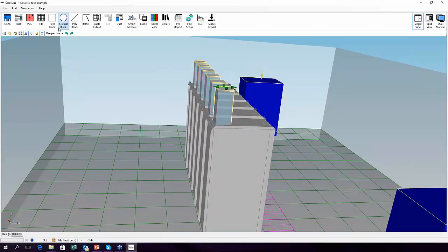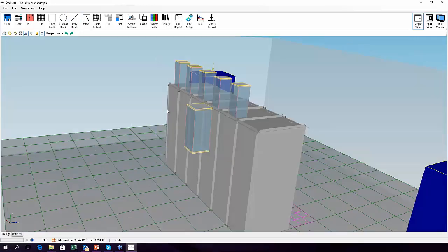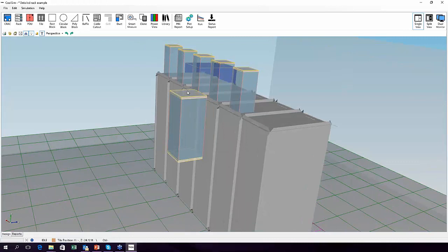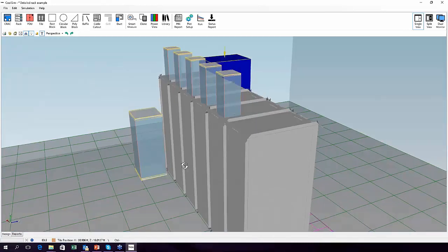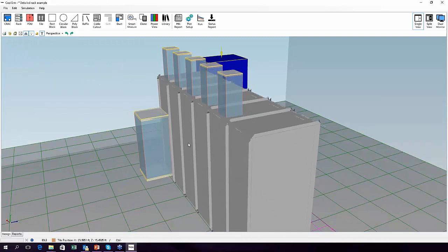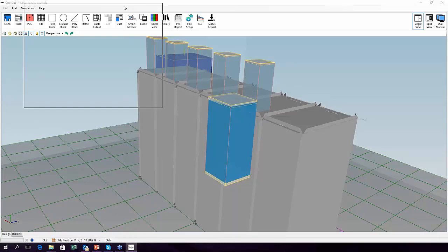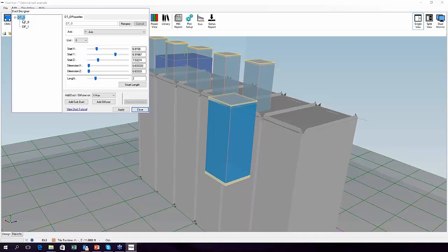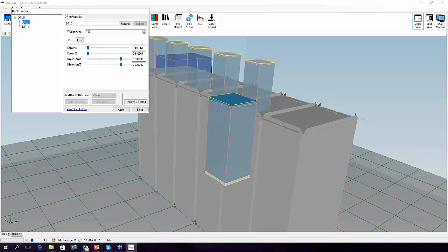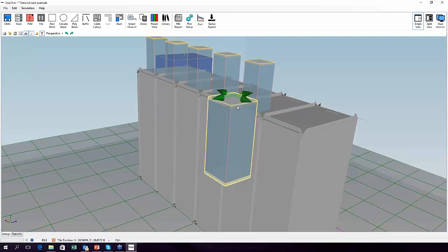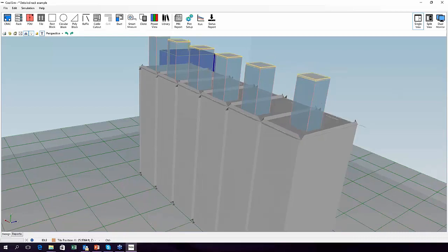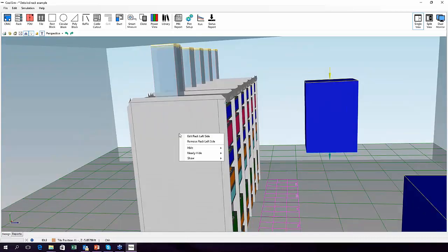This is a fluid block. It's what we call a duct. In Fluent we call it a fluid block, and it's just a block. It's just a duct. Remember, you do have to put a diffuser on the top and bottom because a fluid block by itself won't pass any medium, because it doesn't know where you want it to go in and out. So this is our little duct designer. The little duct designer toolkit comes up, and I have the duct, and then you see I have a diffuser at the top set at 100 and a diffuser at the bottom. I get the height where I want it, and then I poke it through. Remember, it's got to go through so that the diffuser can be seen on the other side.